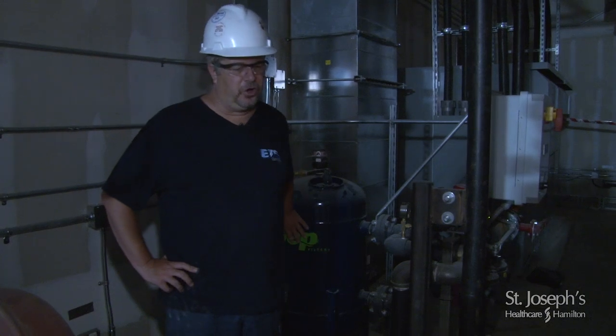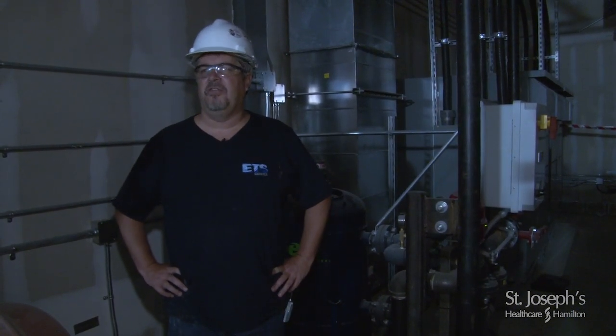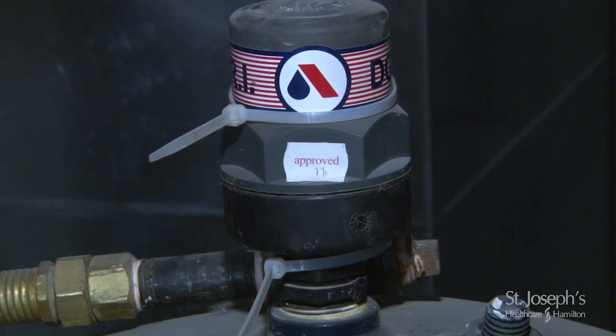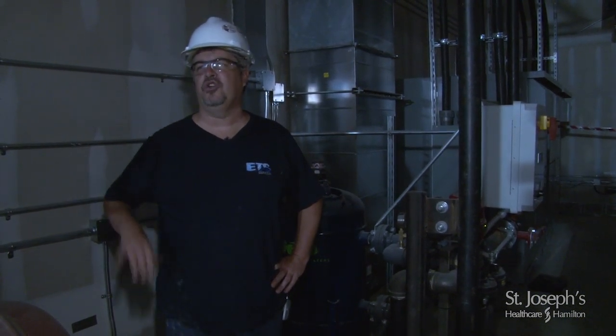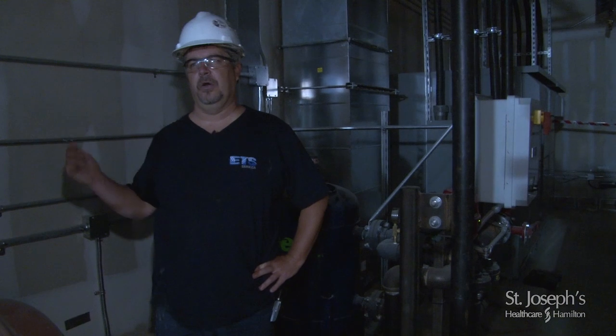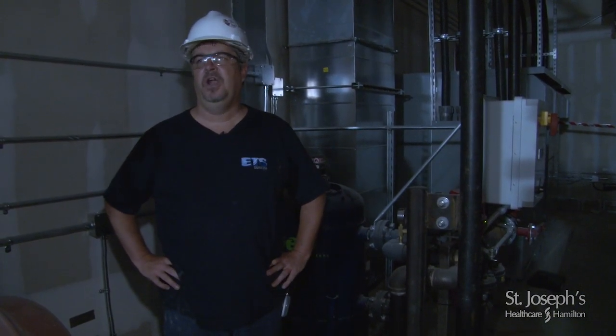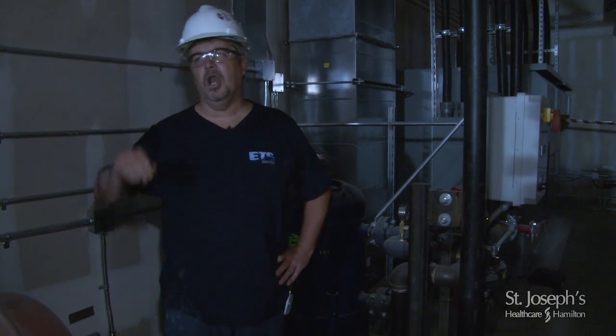Beyond that, the sand media should last 2 to 5 years, depending on the amount of dirt, and based on that, it's more a judgment call. If the unit is purging itself on a continuous basis and that cycle seems to be getting more and more often, it's a good indication that the filter media is no longer doing its job and it's time to change it. Again, a good rule of thumb is approximately 2 to 5 years, depending on how often the towers run. I know the cooling towers here, half are going to be off all winter. That's going to extend the life of the filter media a little bit beyond that.